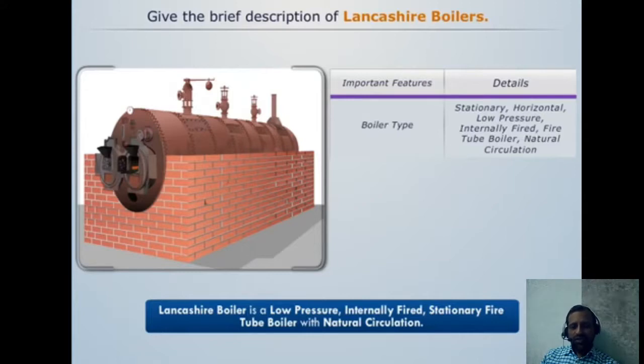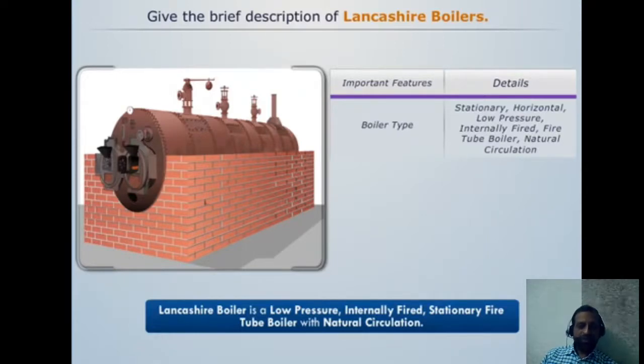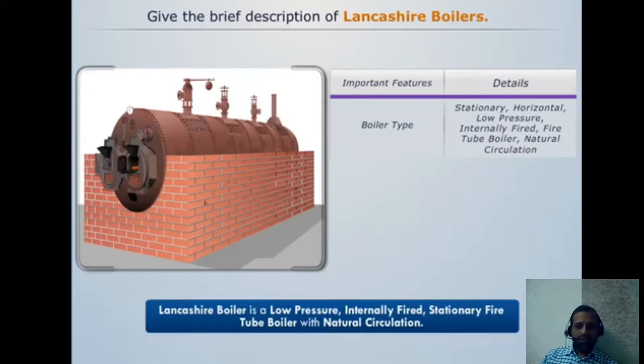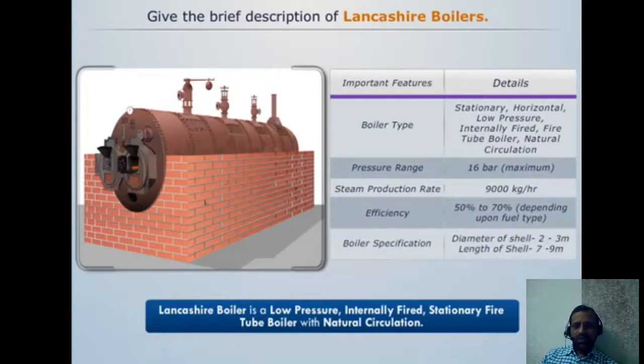The Lancashire boiler is a low-pressure, internally fired, stationary fire tube boiler with natural circulation. The boiler type is stationary, horizontal, low-pressure, internally fired, fire tube boiler with natural circulation. Its pressure range is up to 16 bar, steam production rate is 9000 kg per hour, and efficiency is 50 to 70 percent.